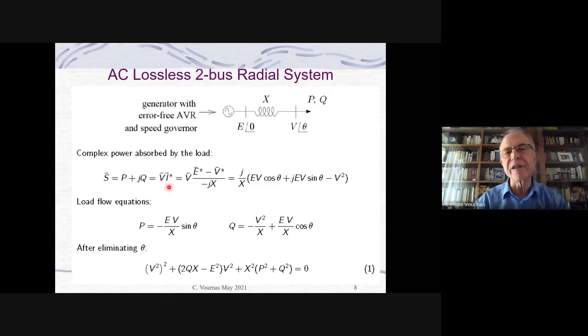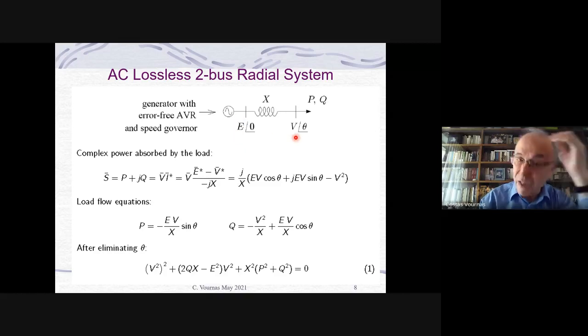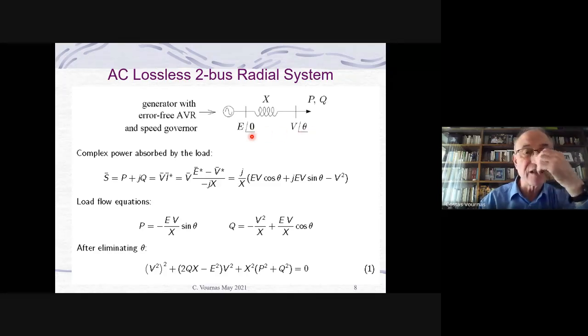V and I are the phasors for voltage and current. And by doing some simple algebra, you can see that the power that you receive at the load is E, the voltage of the source, times V, the voltage at the load, divided by X, the reactance of the line, times sine theta. It is a lossless AC line, but it does have a reactance. And theta is the angle between the load voltage and the generator.